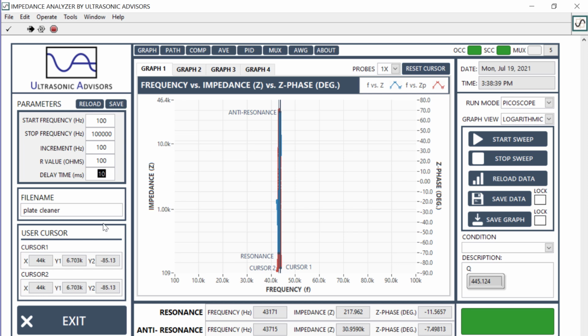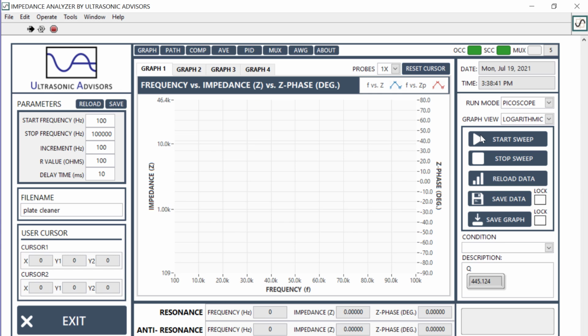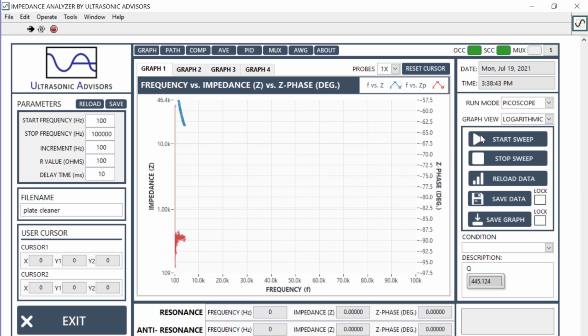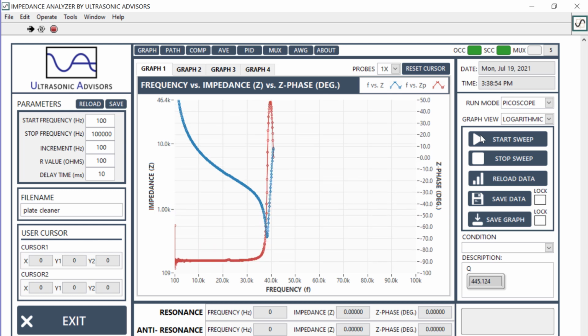Notice this delay time here. It's quite important that your sweeps don't go too fast, or else your instrument will likely provide variable and also incorrect data if you do your frequency sweeps too fast. So that's the 40 kilohertz resonance point there.